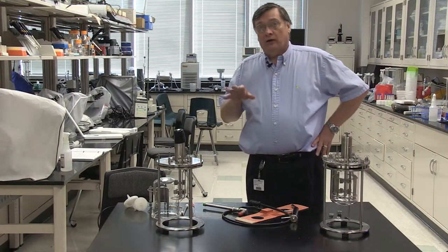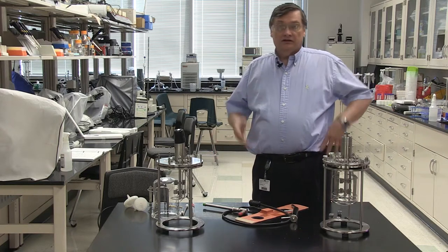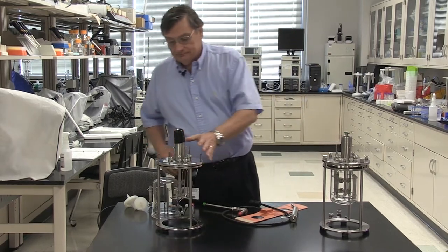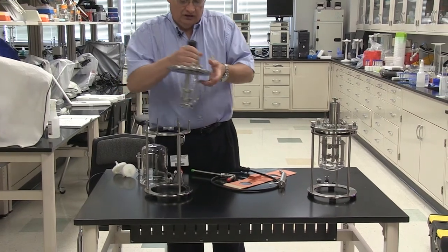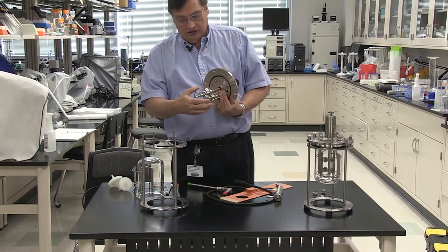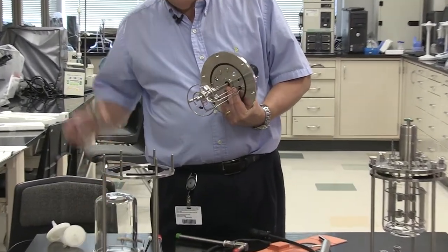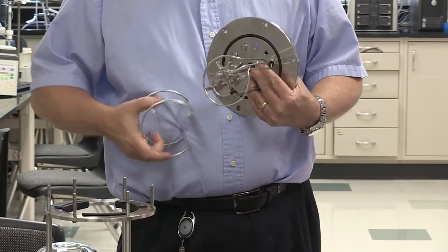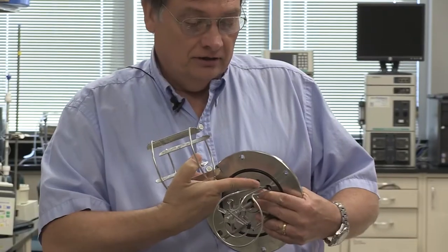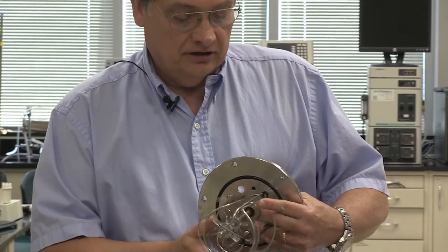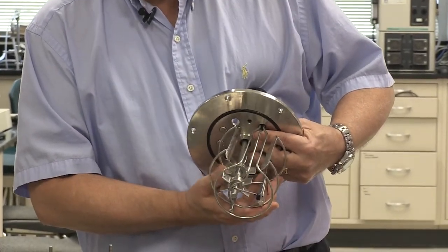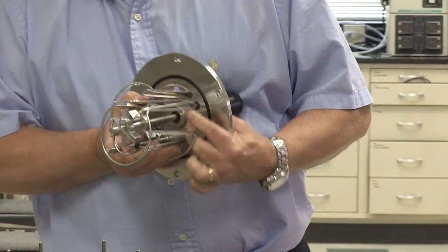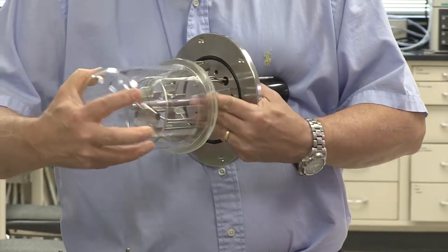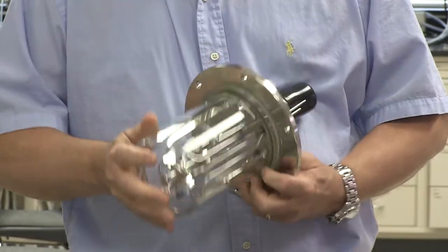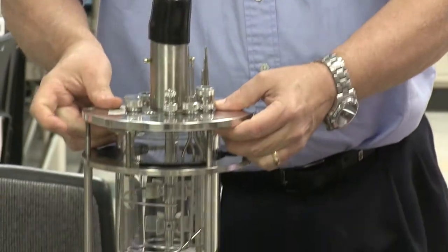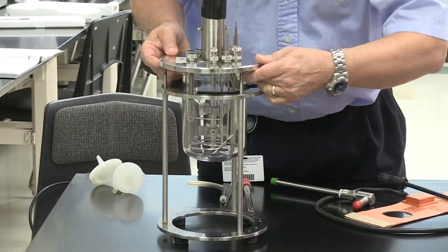Okay, so let's take a look at how we actually assemble the vessel prior to autoclaving it in order to prepare it. Let me get this off. So this is pretty much assembled as it should be. Then we have the baffle to put in. And I prefer to have the baffle, the opening in the baffle, so that the sparger and the cooling are kind of not in its way, right? And so then we slide the vessel on. And see if I can get it together.